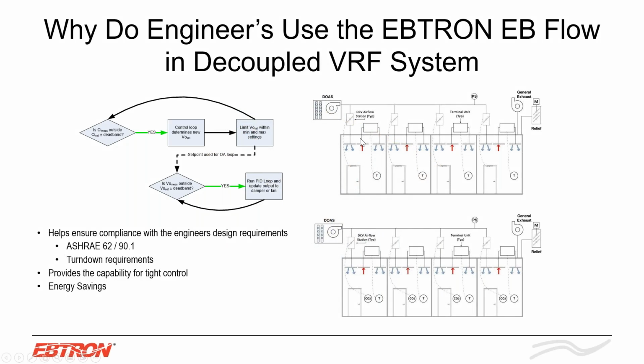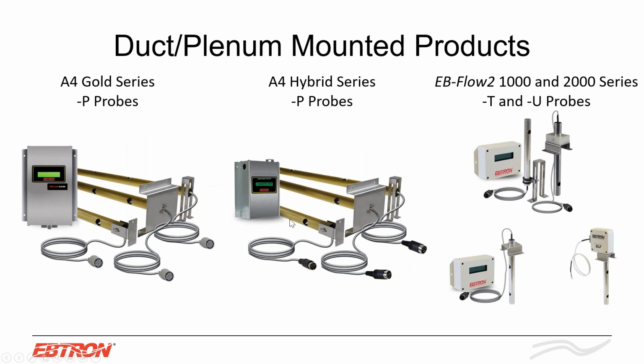And I did talk a little bit about decoupled systems previously, and this is basically the same graph, but where this takes it a step further is, you could have a CO2 sensor going back to a controller and modulating the airflow rate at the terminal level based on our unit, and based on the controller, and based on the CO2 reading in the space, if you're using a decoupled system. And you could also do this the same way with our population counting over the door. So think about classrooms or schoolrooms. Extremely tight control with using the EBFlow products.